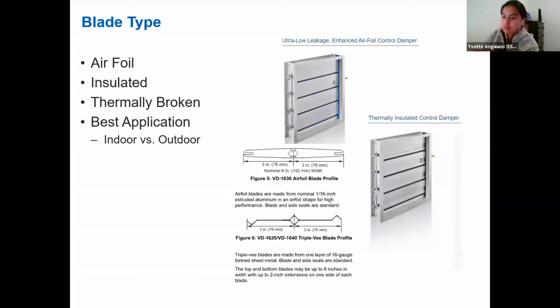So like in your air handling unit, you want to use it where the blade is having an outdoor application, such as the exhaust fan, or the exhaust duct and the outdoor air duct, just to avoid the cold air going through that space. And then for the indoor application, you would want to use these low leakage dampers for your return air duct or your supply air duct, where it's not a concern for coil freeze up.